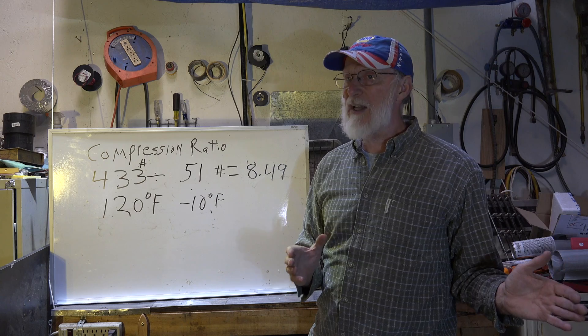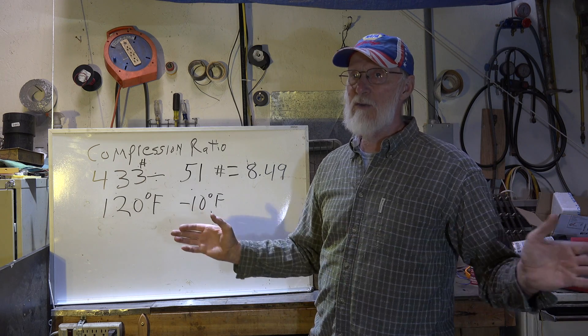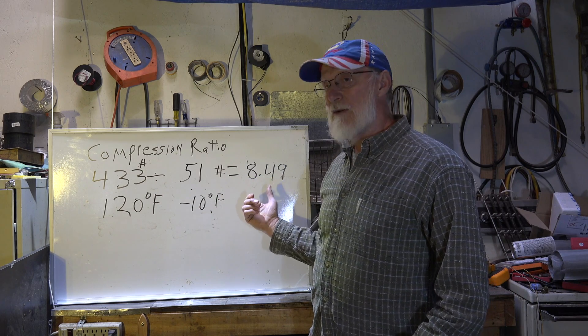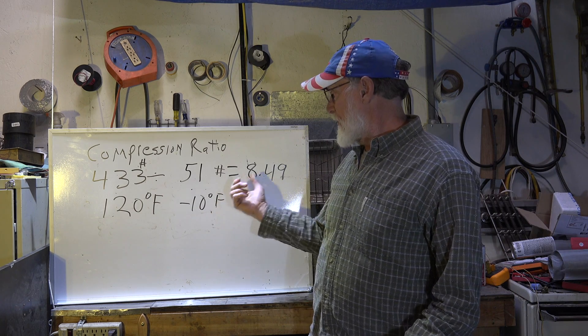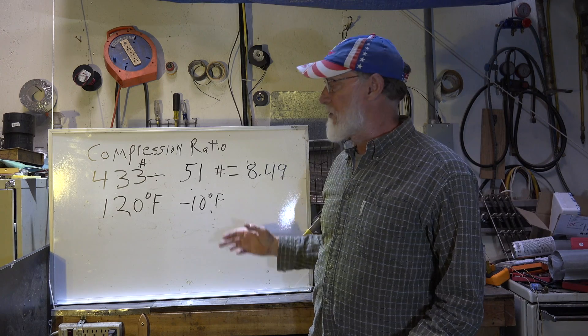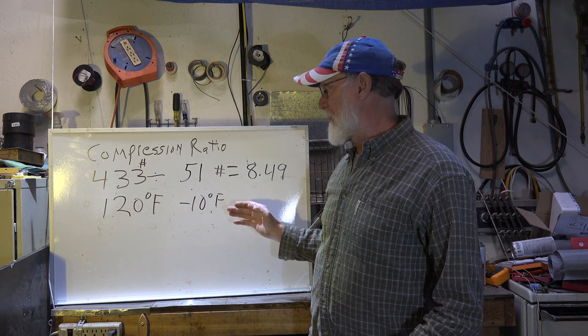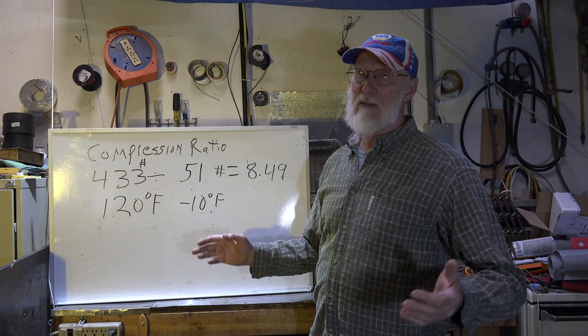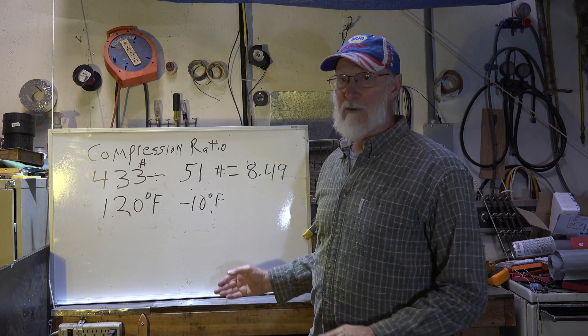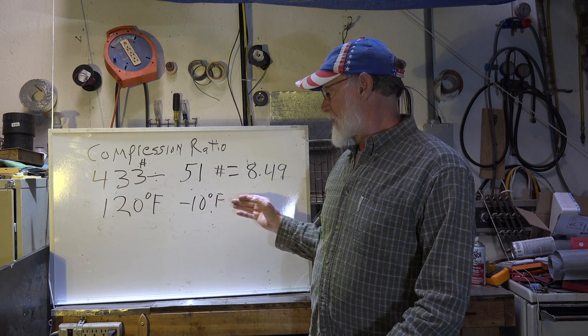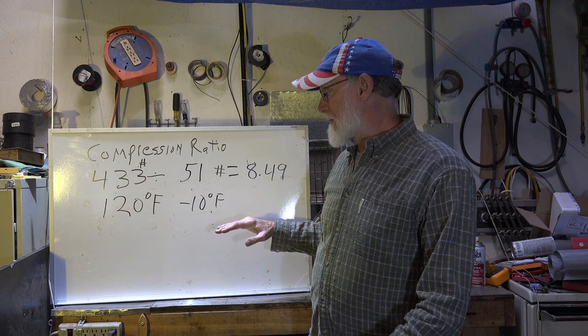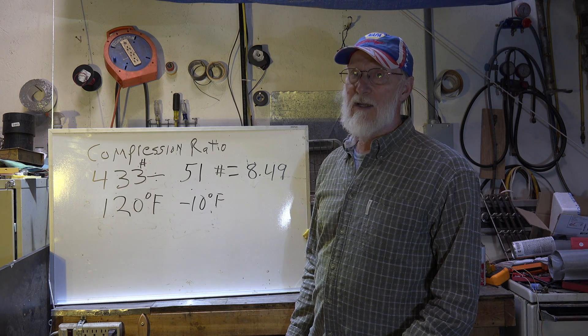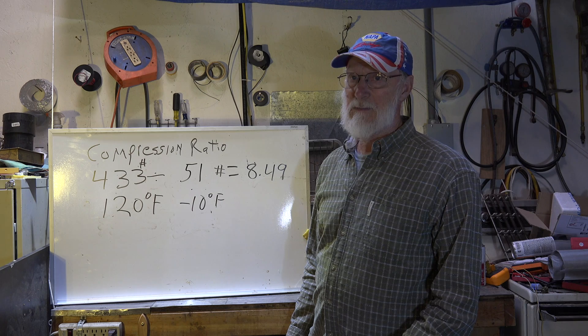It's not going to move as much heat — it's all about moving heat. With a higher compression ratio, you move less heat. If you don't want to think about compression ratio, just look at the temperature difference and the pressure difference — remember, temperature and pressure are related in a refrigeration system. Compression ratio determines how much refrigerating effect you get. That's all for this one.